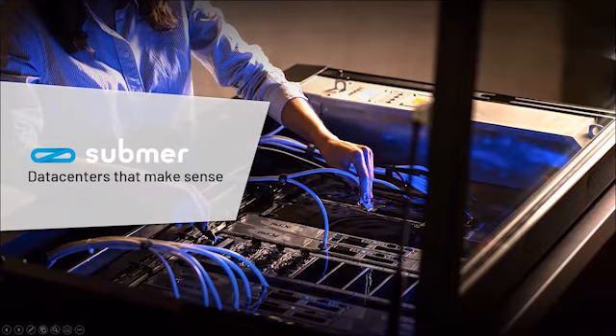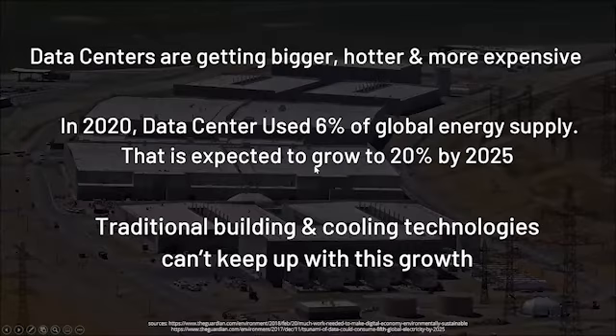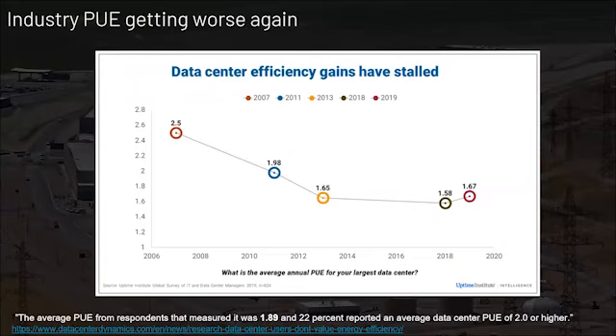What we do is take servers and immerse them in fluid, and I can drive the efficiencies you see back here. I can take this from 1.65 to 1.03 very consistently, down to 1/20th, or 5%, of the power I was using to cool the data center. I reduced it by 95%, and I could do that very consistently.